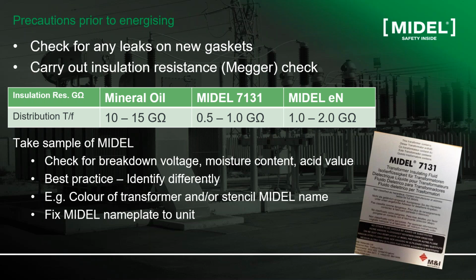And the table in front of you shows just that. For a distribution size transformer, a mineral oil filled one could have an insulation resistance of 10 gigaohm to 15 gigaohm. If filled with synthetic ester MIDEL 7131, it could be 15 times lower, so 0.5 gigaohm to 1 gigaohm, and for natural ester it could be 1 gigaohm to 2 gigaohm. These are typical value ranges, and I wanted to show them here so that anyone doing the retrofill and measuring will not be alarmed by these lower values compared to mineral oil, because usually lower values will indicate a change in the insulation within the transformer.